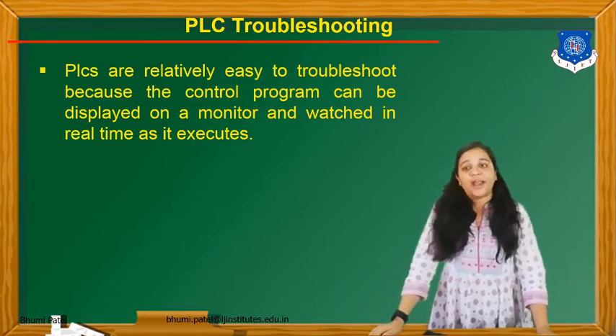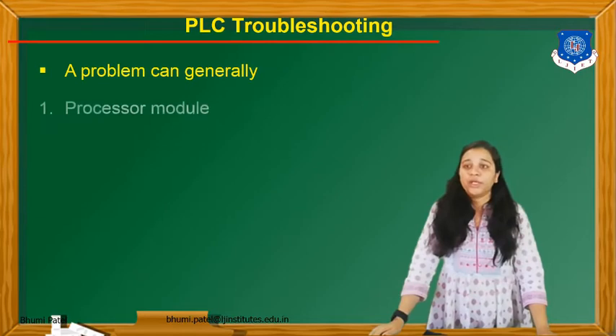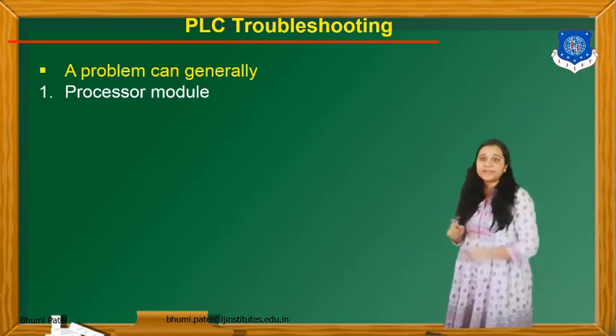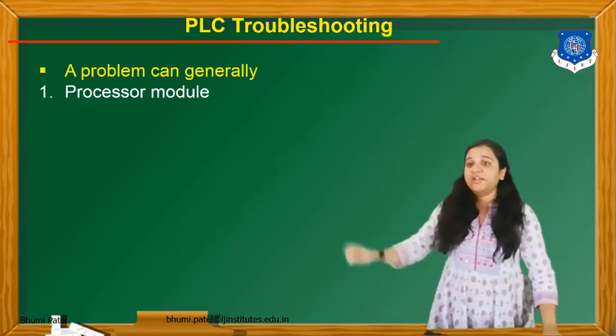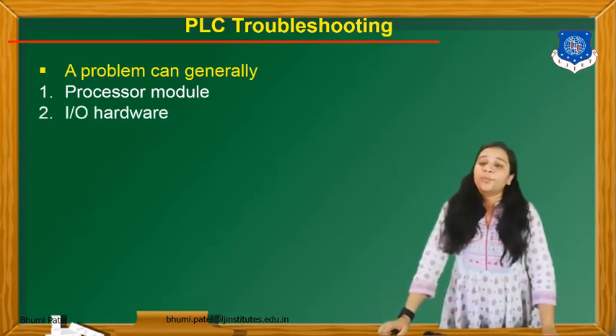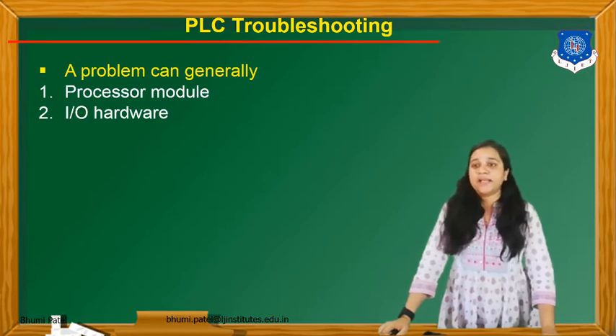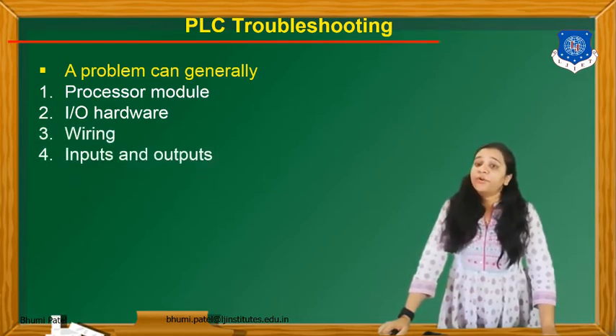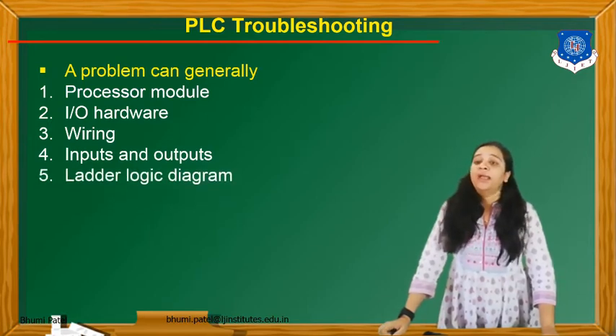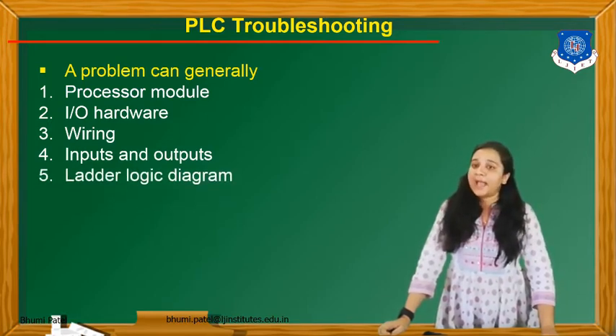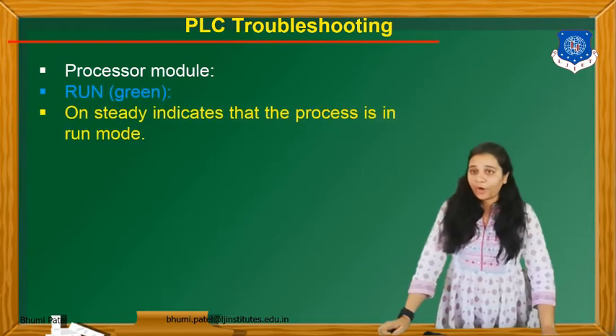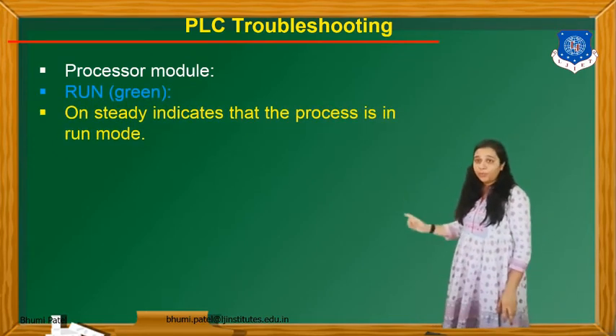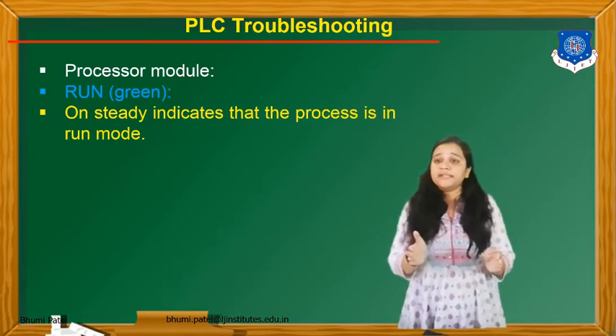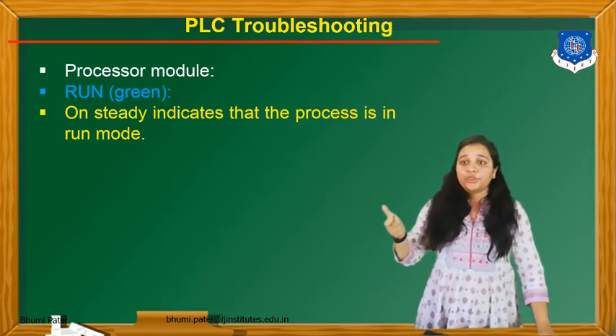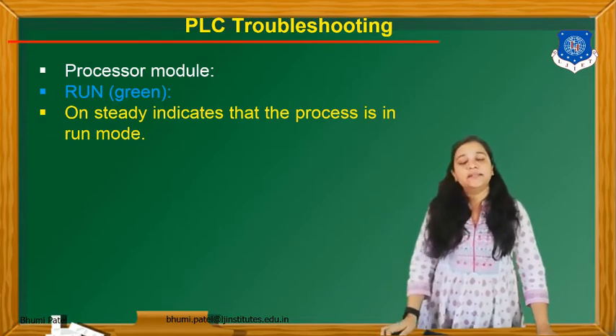So we can continuously change the data during its execution time. Okay, which factors are included in PLC troubleshooting? The problems can generally arise in, first, the processor module, then the input output hardware connected with this PLC hardware, then the wiring, then the fourth one is the different types of input and output, and the fifth one is the ladder logic diagram. So first of all, what is the troubleshooting in the processor module? If the module is in run mode, the green light on the PLC hardware is steady, which indicates that the processor is in run mode.